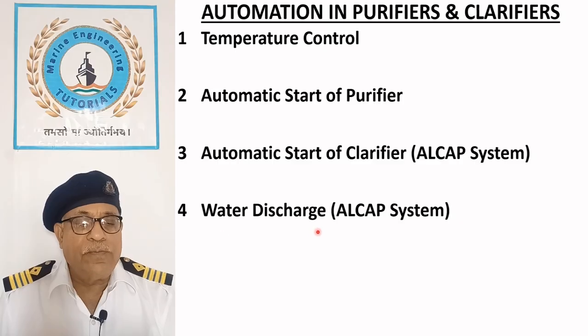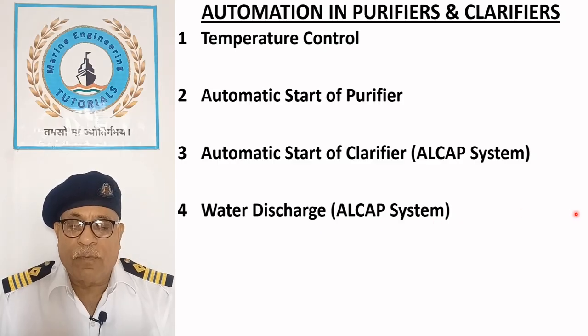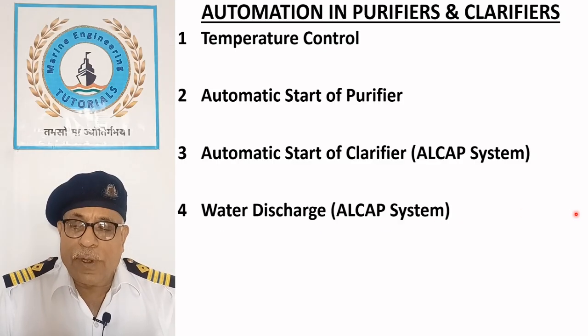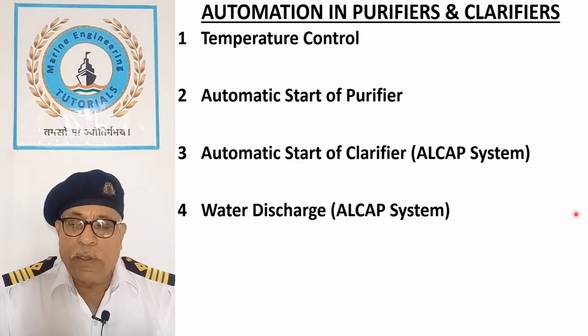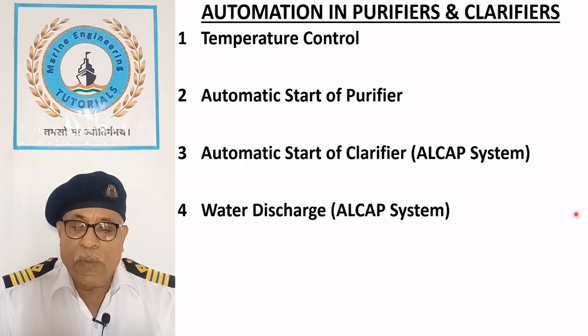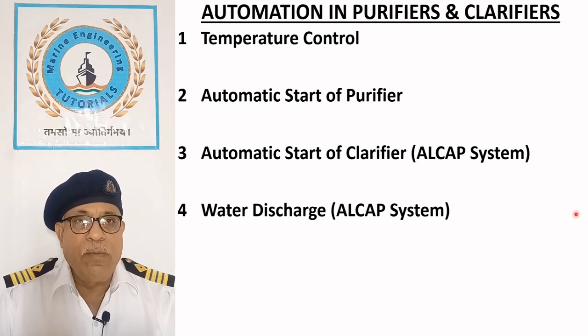Water discharge in ALCAP system. The water transducer continuously monitors the water content in the clean oil outlet. When the water content exceeds the preset limit, it activates the water drain valve for a specified period.